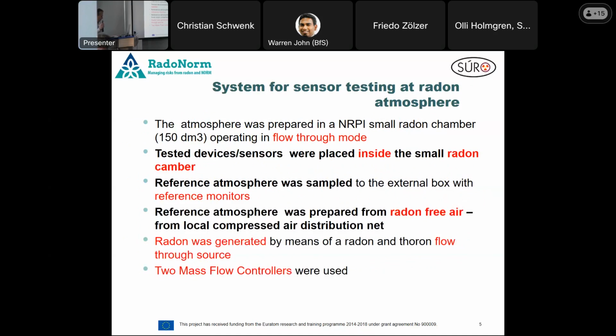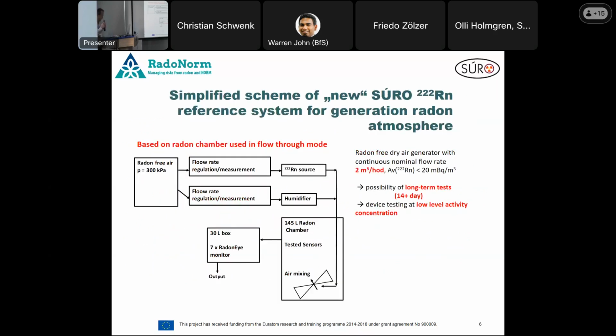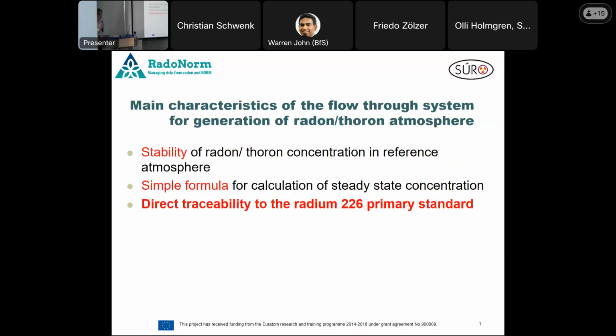For the test of radon sensors carried out as part of this project, we used a small radon chamber connected to the radon source. Both source and chamber operate in flow-through mode. Air was taken from a radon-free air generator and flow was set using a Bronkhorst gas regulator. Tested devices were placed inside the radon chamber, and the reference atmosphere was sampled to an external box with a reference monitor.